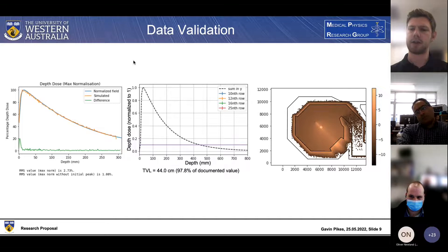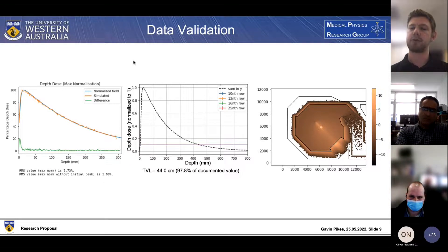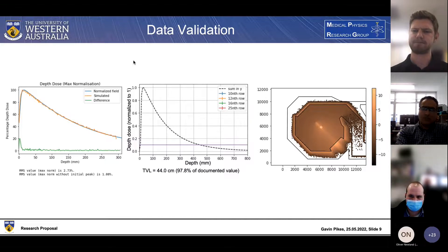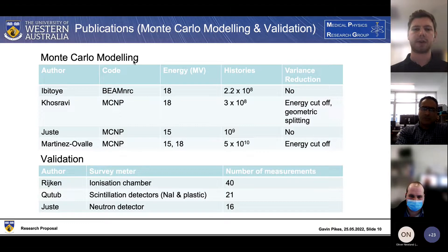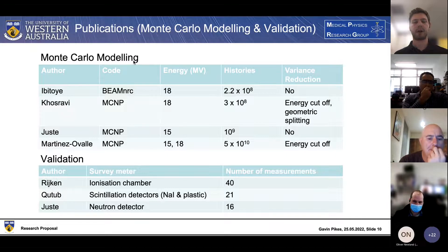This does make validating against radiation survey results taken outside the bunker a bit tricky as our relative error is quite high there, but we've got a reasonably accurate set of results within the bunker room itself. We'll likely need to take some measurements of energy deposition there and compare our data to reduce the relative error problems outside the bunker. In terms of publications, I split these into three main sections: Monte Carlo modeling, data validation, and optimization. A couple of different papers have made similar Monte Carlo models of linac bunkers.